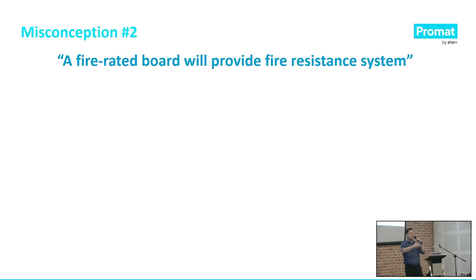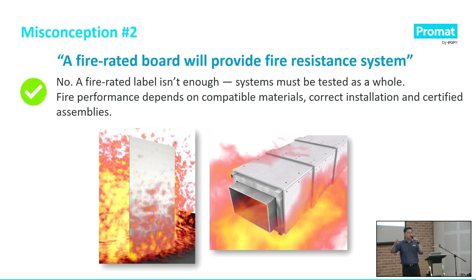It's just used as a reference, for ease of understanding—you can say, oh, you have a fire-rated board or not. But then we'll zoom in on what it actually means by fire-rated board. In our fire protection world it doesn't mean anything on its own, because when exposed to fire, it's just a board. How are you going to rate this board? You cannot. The so-called 1 hour, 2 hour, 4 hour fire rating cannot come from a single board—if you throw it into real fire testing, you have to build it up as a system.